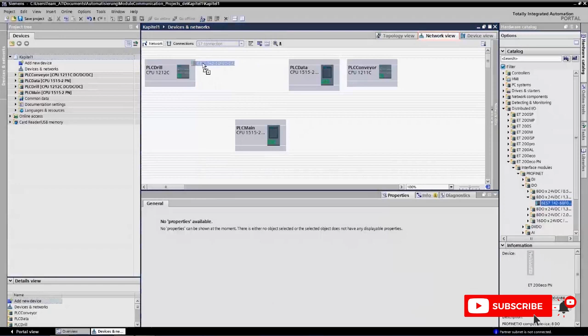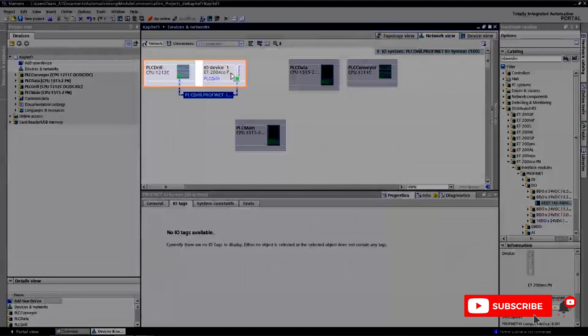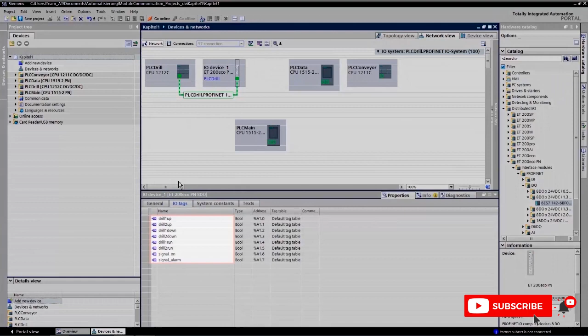How is it done in the TIA Portal? In the TIA Portal you comfortably define the connections between the devices in the network view. To set up the peripheral configuration, you just connect the CPU to the peripheral device. The address assignment for subsequent control over your program is performed by the TIA Portal. However, you should assign symbolic names for your variables to simplify the programming process at a later date.